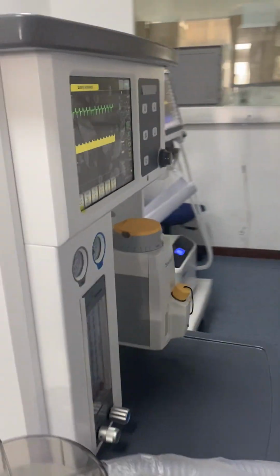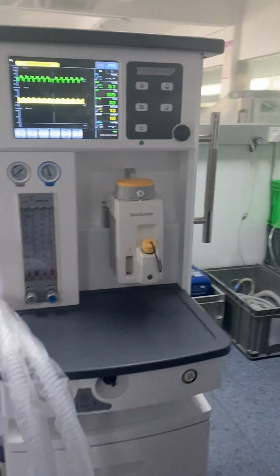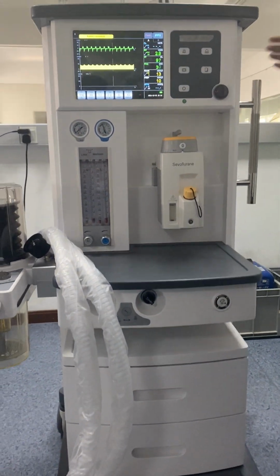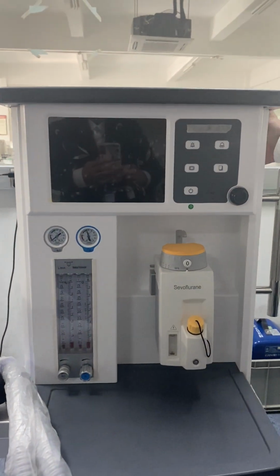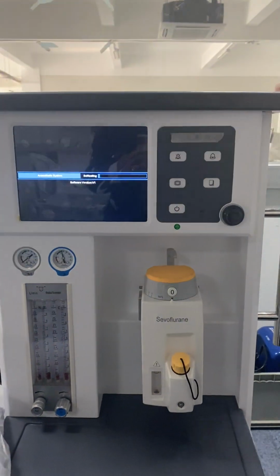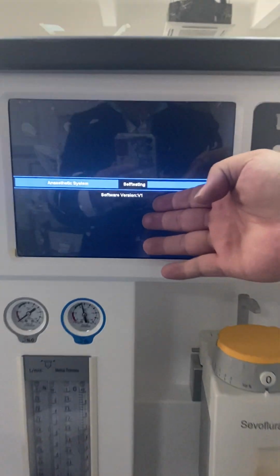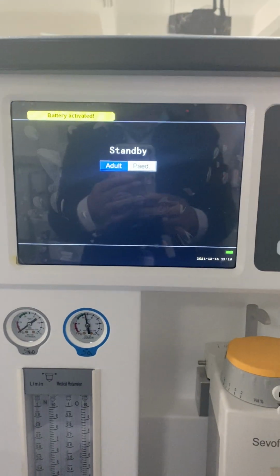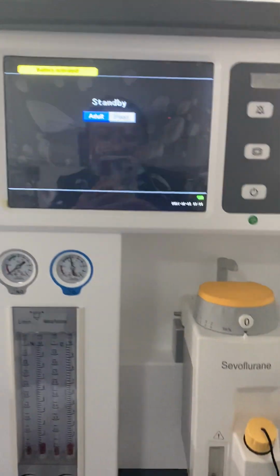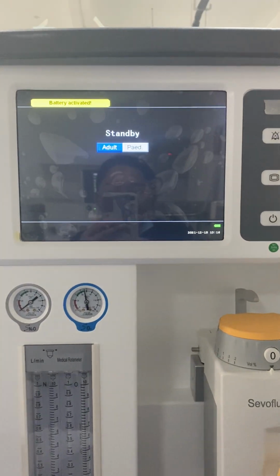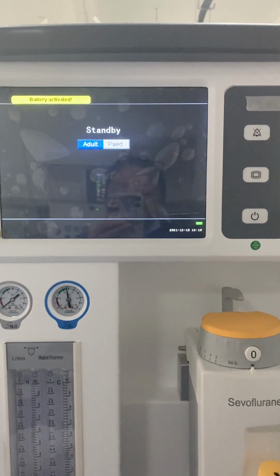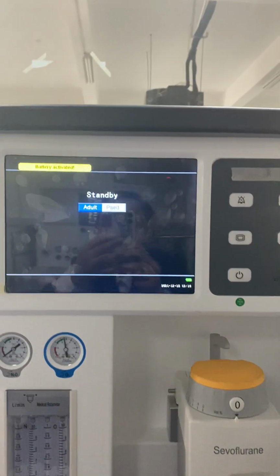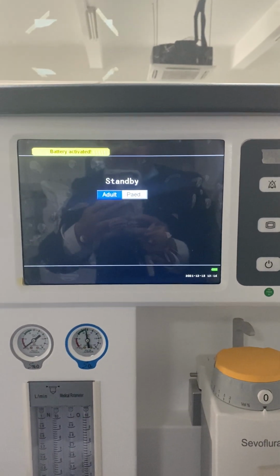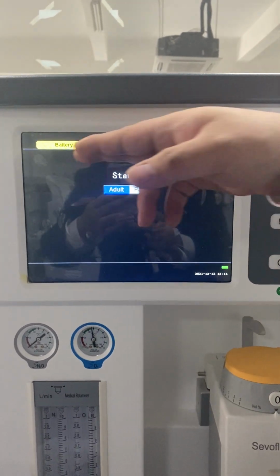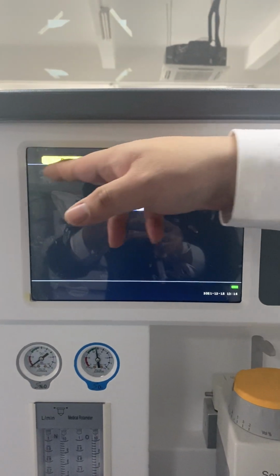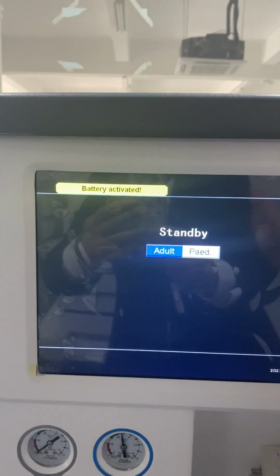For now, let's start the introduction of the machine functions and parameters. When we switch on the power, you will first see the self-testing on the screen. During these 3 seconds, the machine is automatically testing itself. This ensures there is no damage to the patient and that the machine itself is in good condition. After the self-testing, if there is any problem, it will be shown on the upper side here in yellow or red color.